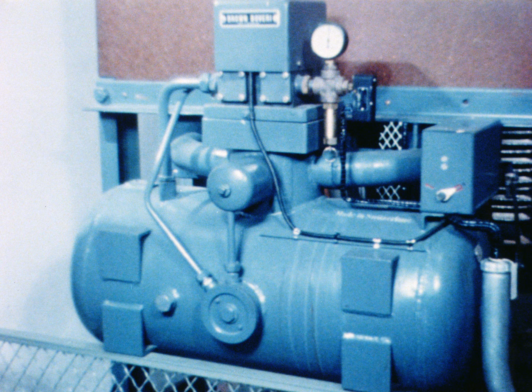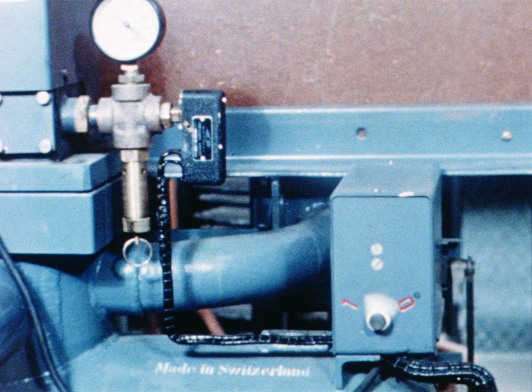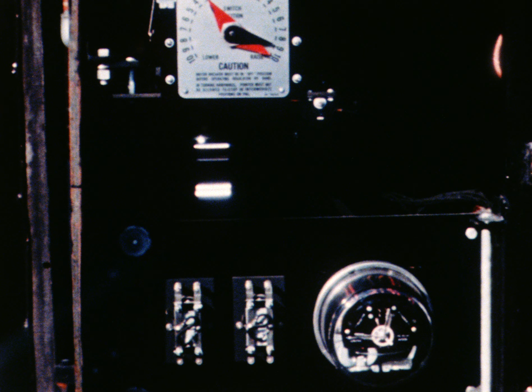In our homes, a switch controls one or at most a few light bulbs. But a circuit breaker in a substation controls enough power to light up a fair-sized town. In less than 1/10 of a second, the power can be cut off. Automatic circuit breakers are of various types. Some of them operate in a sealed bath of insulating oil. There is other important equipment in the substation. Automatic voltage regulators, sensitive to every increase or decrease in the load, ensure a constant and exact flow of electric power.